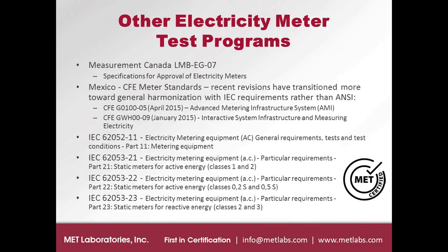We do offer other test programs. I mentioned the Measurement Canada program under the RTO1 program in Canada. That's actually the only test lab that's approved or recognized, I should say, by Measurement Canada for performing tests and having that data recognized by Measurement Canada. It's a little restrictive in that it's only for previously certified meters, and we're still following the test plan that's provided to the manufacturer by Measurement Canada directly. However, we can help out and generally get those tests done in maybe a little quicker fashion than if you get in the queue with Measurement Canada.